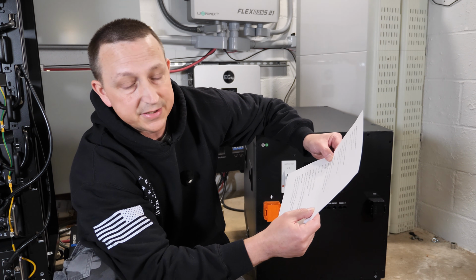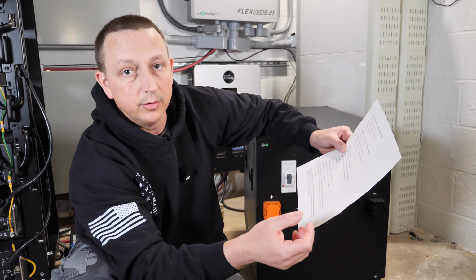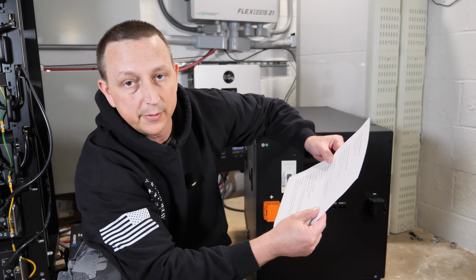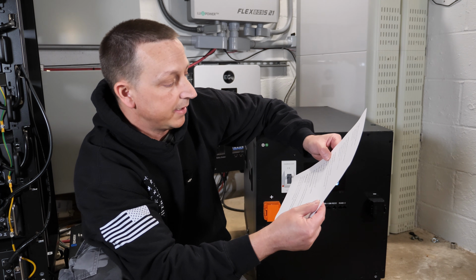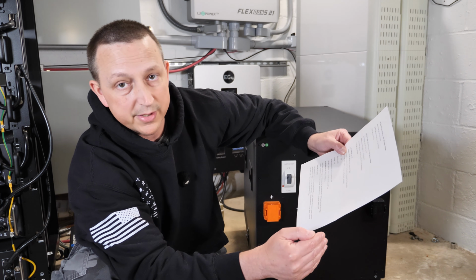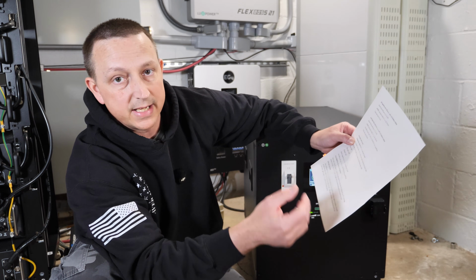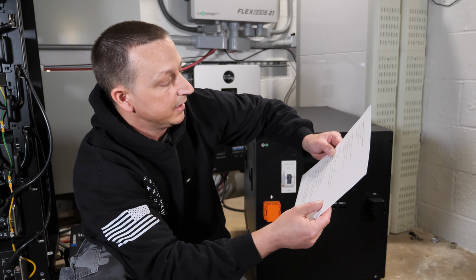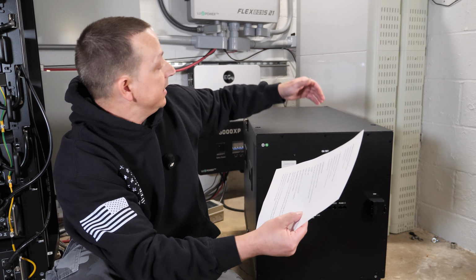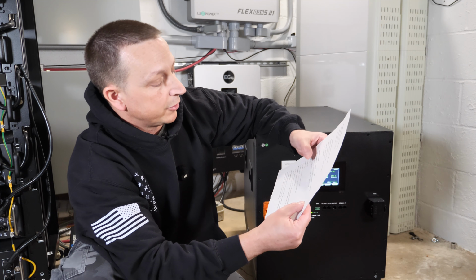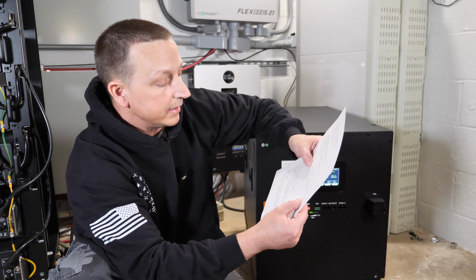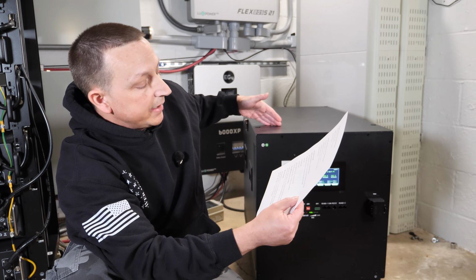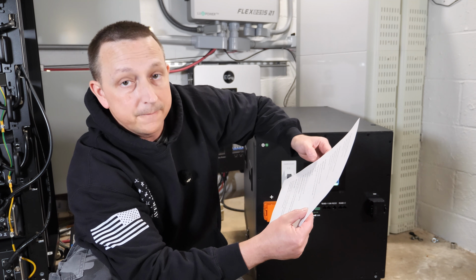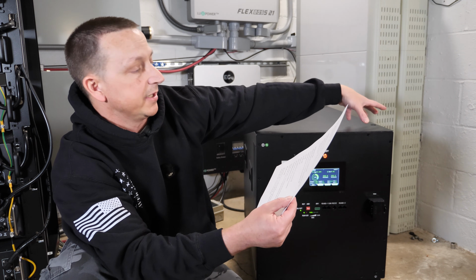Before the test started, the average temperature was anywhere from 74 to 76 degrees Fahrenheit all over. Later on, towards the end of the test when everything leveled out, the cells in the very back were around 95 degrees Fahrenheit, and the ones towards the front were around 105 degrees Fahrenheit, because everything up here gets pretty warm.